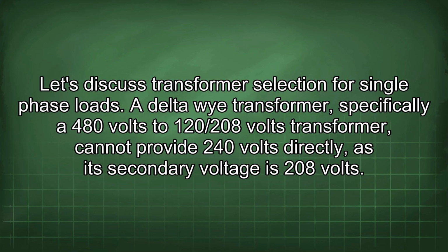A delta-Y transformer, specifically a 480 volts to 120/208 volts transformer, cannot provide 240 volts directly as its secondary voltage is 208 volts.